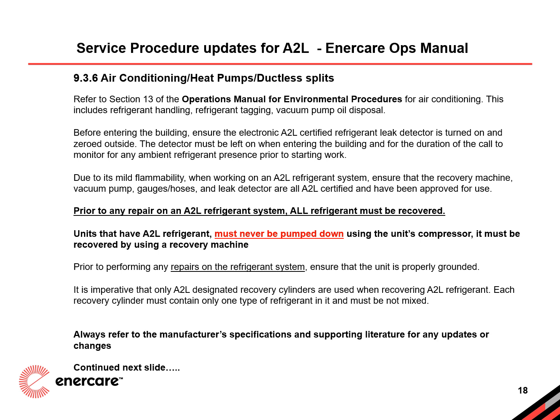Additionally, the process for managing A2Ls has shifted to further prioritize safe handling. Instead of relying on a scroll compressor to pump down refrigerants, technicians are now required to recover the remaining charge using A2L-rated recovery equipment and dedicated, clearly marked recovery cylinders. This approach mitigates risks associated with overpressure, excessive heat, and potential refrigerant fractionation, particularly for blends like R454B.